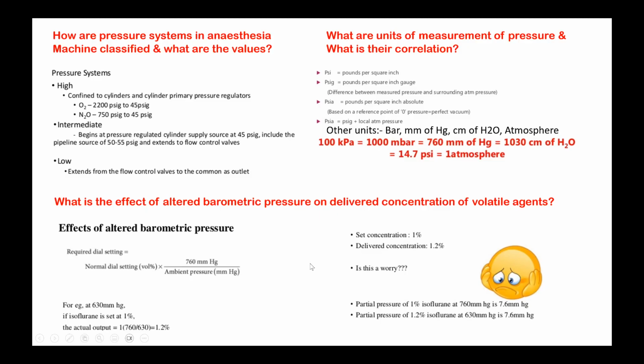So a common question examiners ask is, do you have to recalibrate the vaporizers at a higher altitude? The answer is no, because the partial pressure is the one which determines the efficacy of the volatile anesthetic agent. So it will not alter. Even though the delivered concentration will be higher, it will compensate for the low atmospheric pressure. So the partial pressure will be the same, and there is no need for making adjustments in the vaporizer.